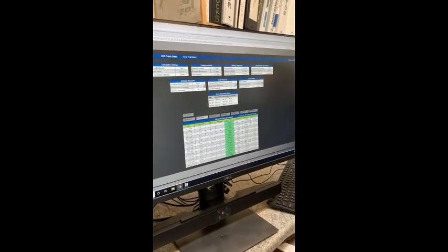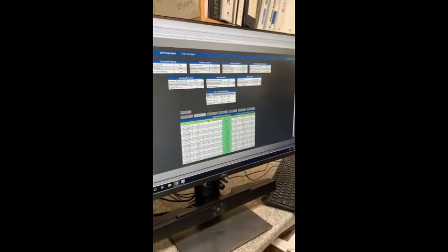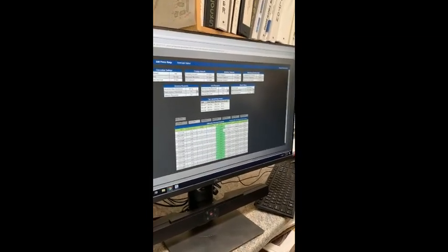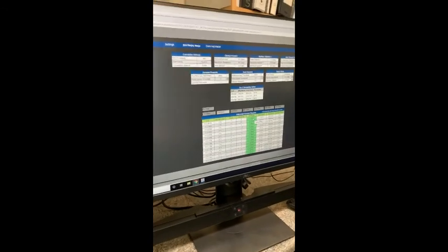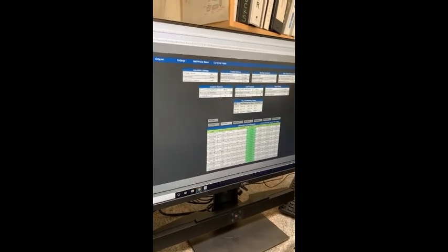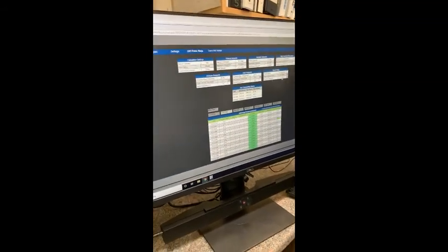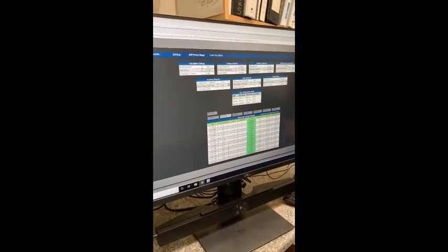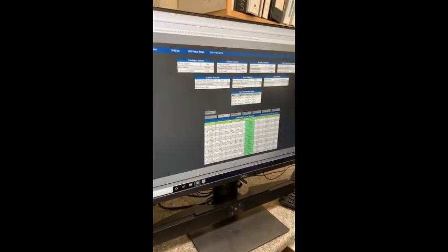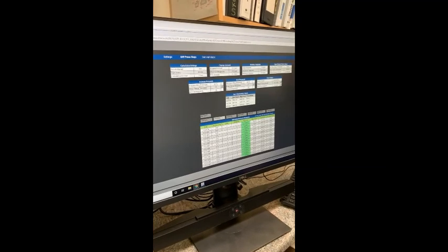The plus and minus ones are not actually degrees or anything. It's just a point: the negative one means you can decrease, and positive one means increase, and it says how many. There's a whole bunch of settings here that are part of the sequence that say how you increase and decrease based on how many are demanding increase and decrease.